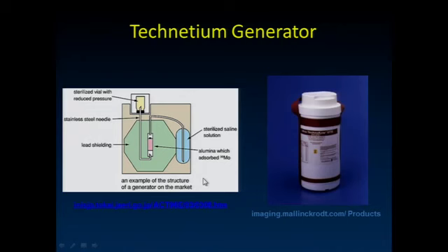developed around technetium. The other thing that's nice about technetium is we can really get technetium fairly readily using a molybdenum generator. So here's alumina adsorbed with molybdenum, and as it decays, some of that decays to technetium, it becomes water soluble in that. And so here's a sterilized solution of saline connected through that column via this tubing.